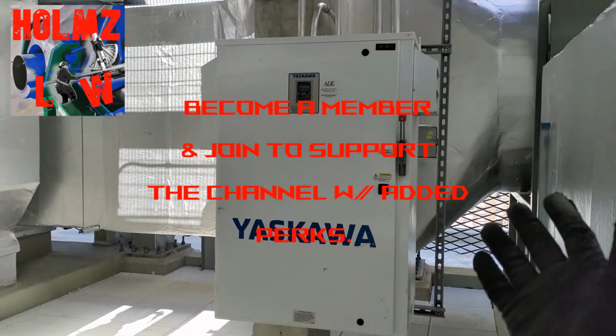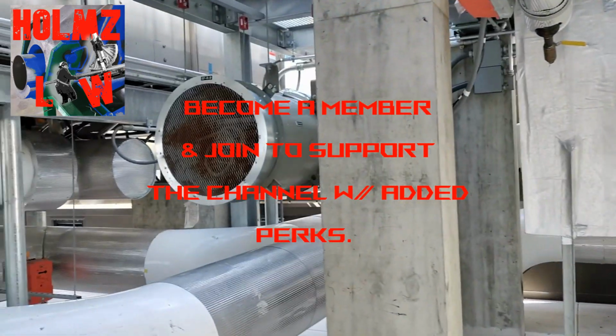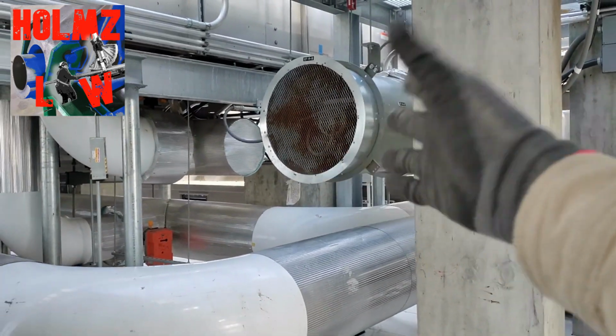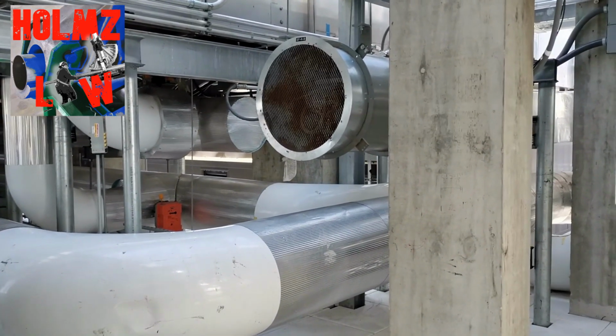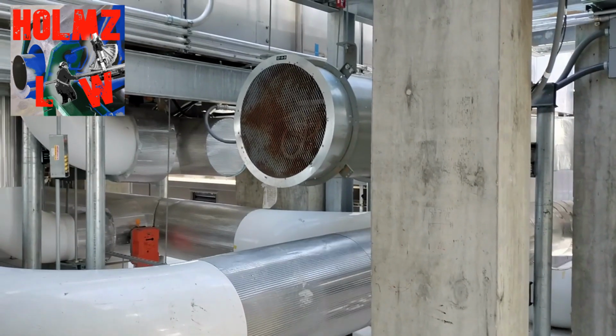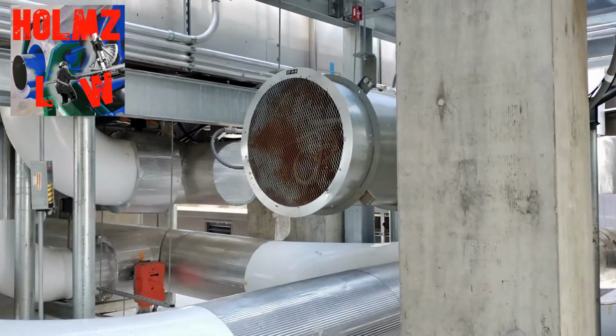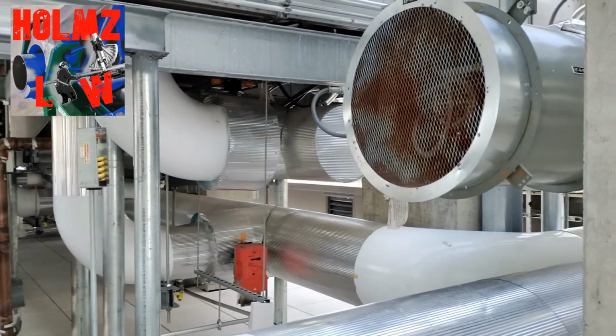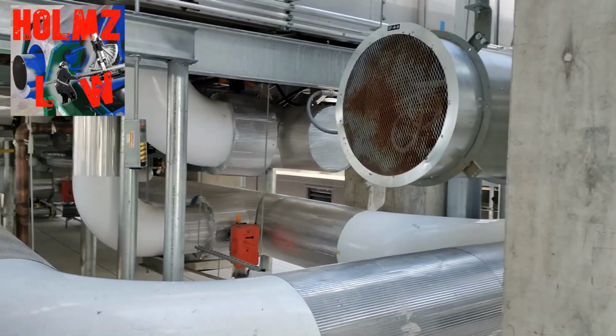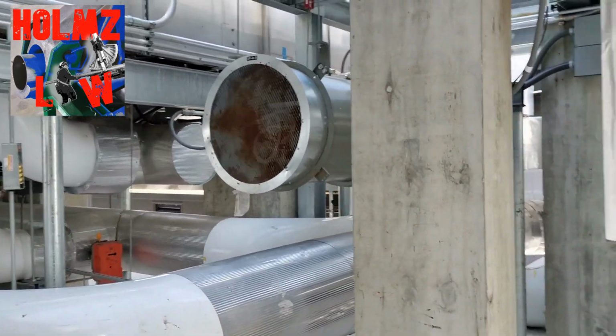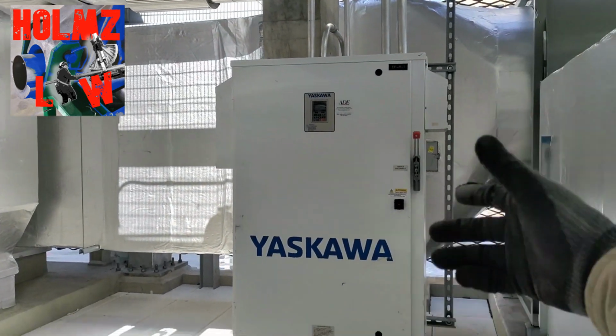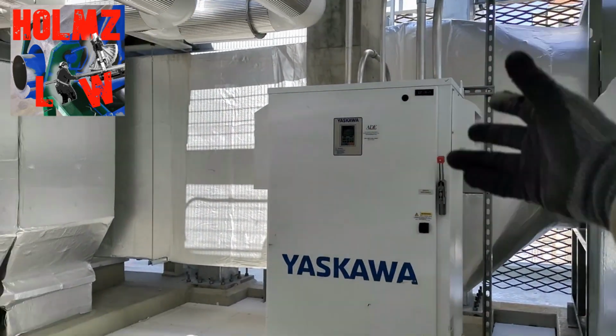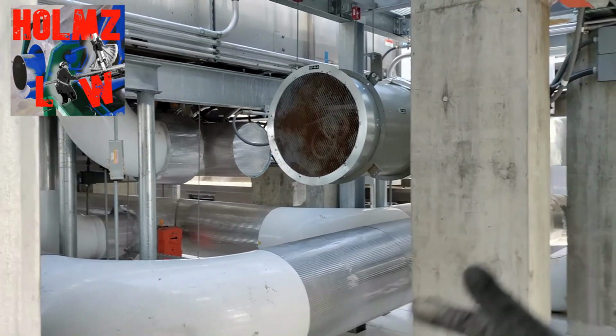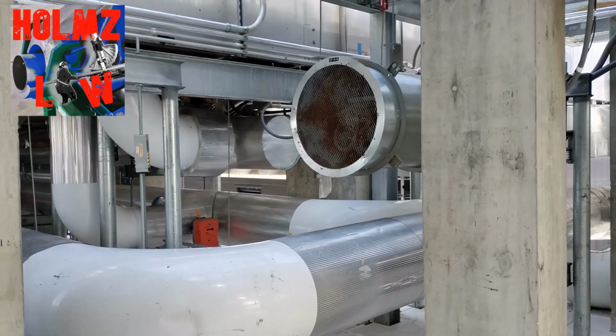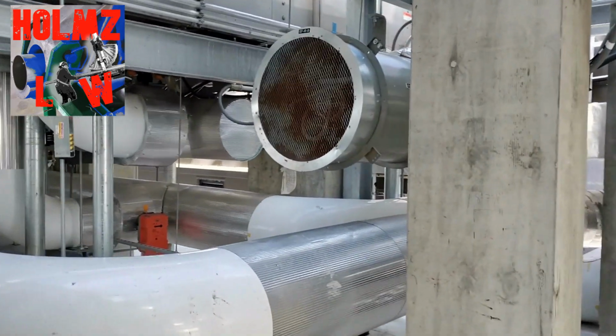You'll find a lot of these exhaust fans up on the roof. There's nothing really much to them. Basically, you bring power to your VFD, and then you bring your motor to the VFD as well. It's not that complicated. It's more about the mechanical side, figuring out where and how you're going to mount your VFDs, where your pipe work is coming from, where your feeds are coming from, and planning all that out.